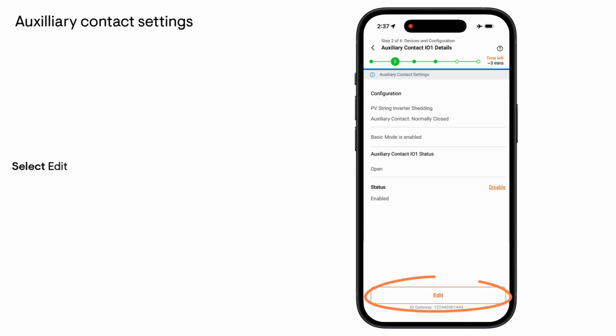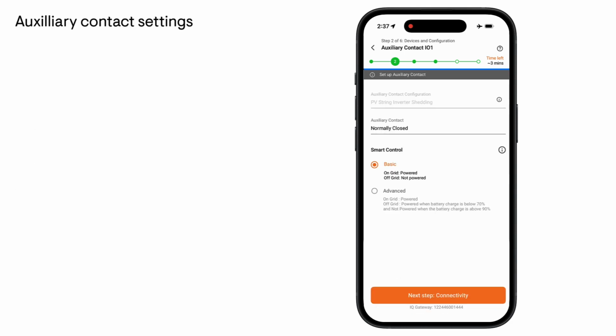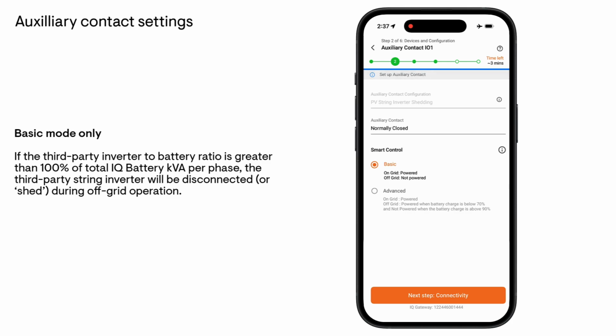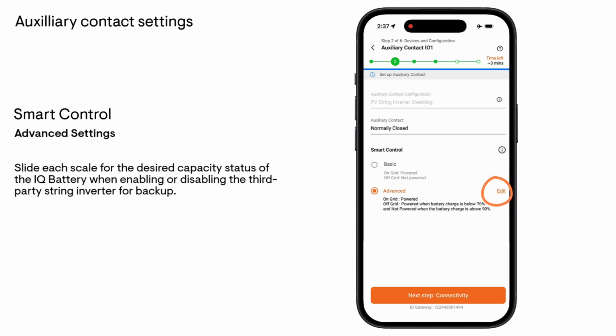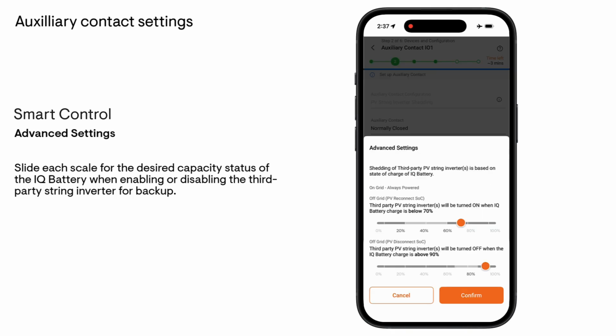Auxiliary contact modes. 2 operating modes are available. Basic only mode. This mode is typically used when the string inverter capacity exceeds the battery output capacity. During backup operation, the auxiliary contact opens and prevents the string inverter from operating. Smart Control allows the string inverter to continue operating during backup. The installer can select a percentage of battery capacity using the configuration slider.